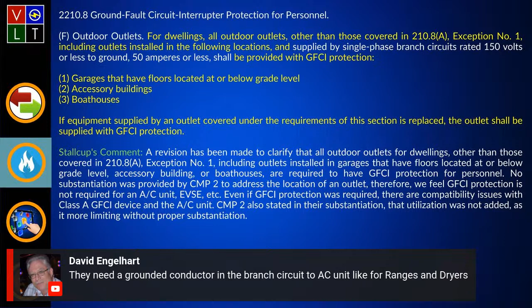So I just installed one, and they did require a grounded conductor to EGC. I asked the customer if he'd like this on GFCI protection since it's in a garage. The equipment does have integral GFCI protection, and he said he's fine with it. If he has to sell the house someday, he might need to bring it up to code and put it on a GFCI, since it's a cord and plug connected installation. But he was fine with the integral GFCI protection.